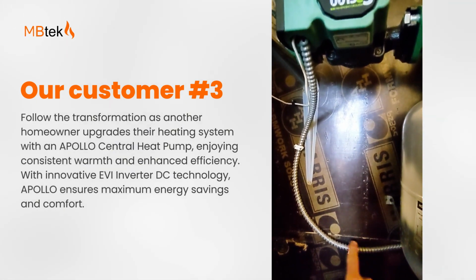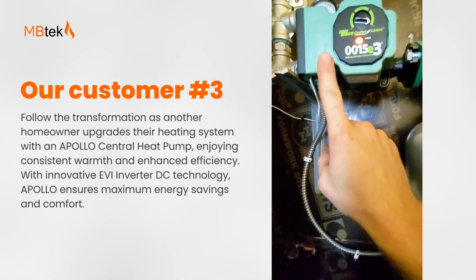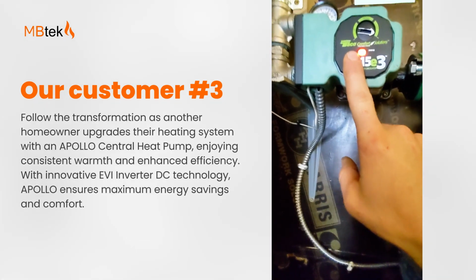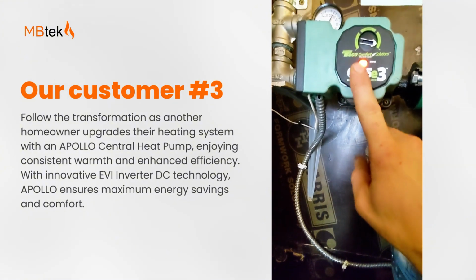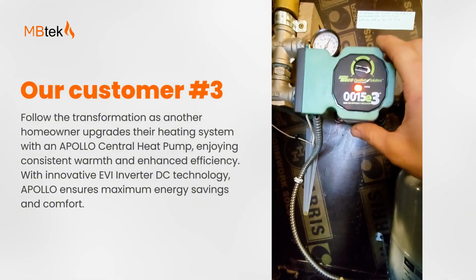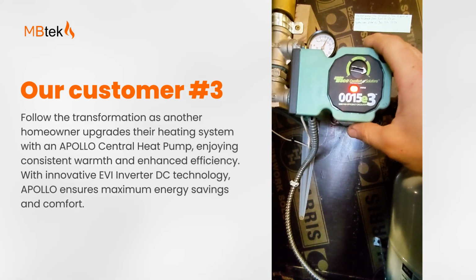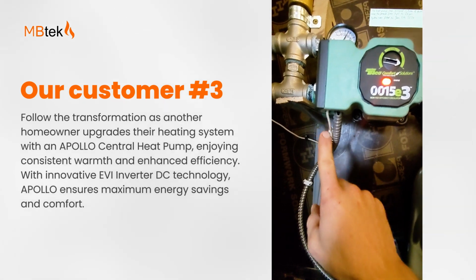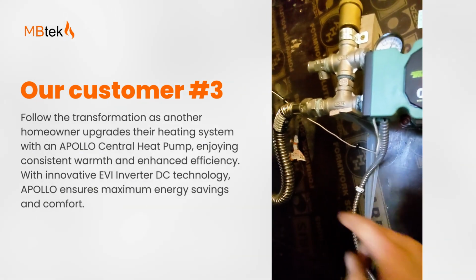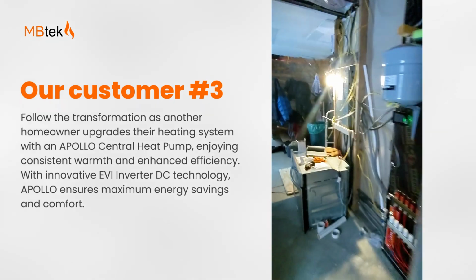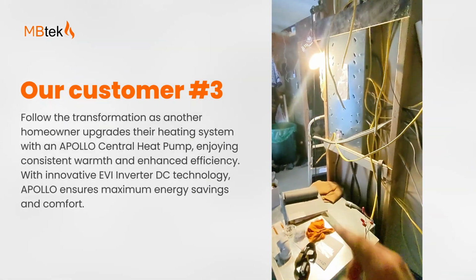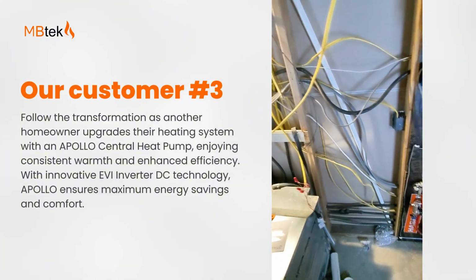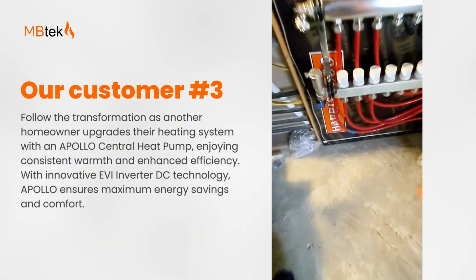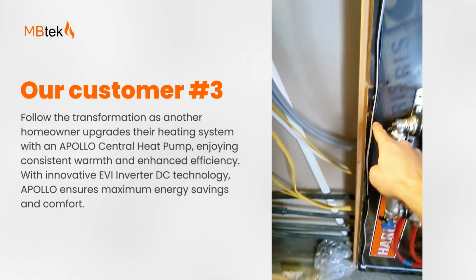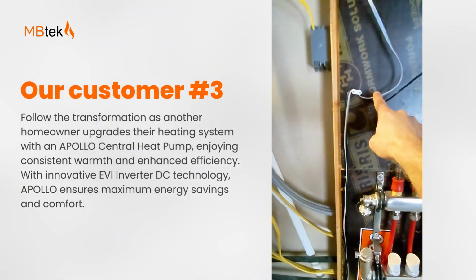So terminal 1 gets that wire and runs it to the, excuse me, to the circulator pump. So the heat pump outside is entirely controlling that circulator, and then I just have a white neutral wire that runs back to my breaker panel to complete the circuit so that the pump runs in the first place. Now again, the communication wires, I just have them tacked temporarily into place right here.